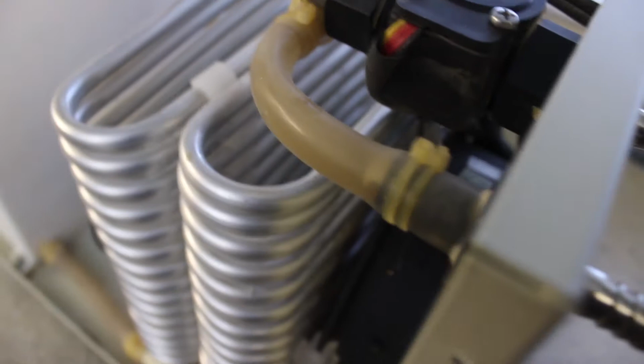On the back we have an inlet and an outlet for the water. The inlet comes back in from whatever laser cutter has been working through, goes through a little T-piece, a Y-piece, into both of these coils, these cooling coils. From there it goes down to the bottom - it's pretty difficult to see, but there's the return, which goes into the bottom of the tank and filters its way through the tank and sits there.